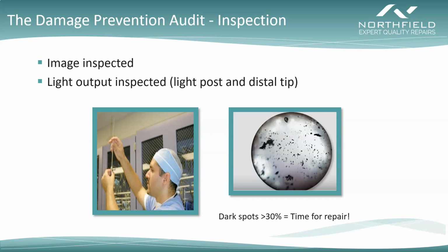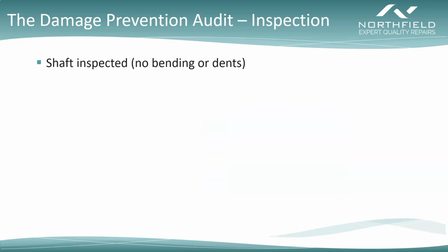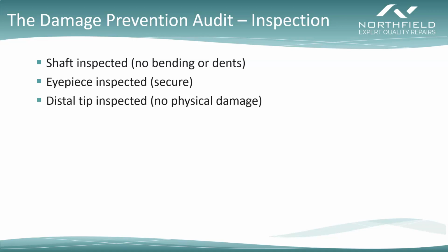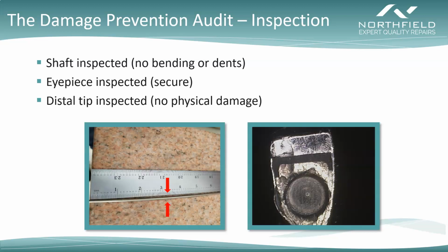So again, if this is not part of your regular inspection process, it's going to allow scopes that don't have proper lighting to make it into the surgeon's hands. And again, that's going to affect that procedure. Now, next in the inspection process, we want to inspect that shaft to make sure that there's no bending and there's no dents. We also want to inspect the eyepiece to make sure that it's secure and there's no cracks. And we want to inspect the distal tip to make sure that there's no physical damage.